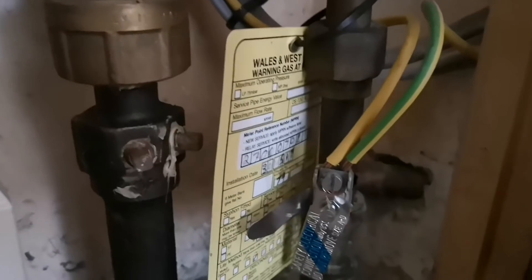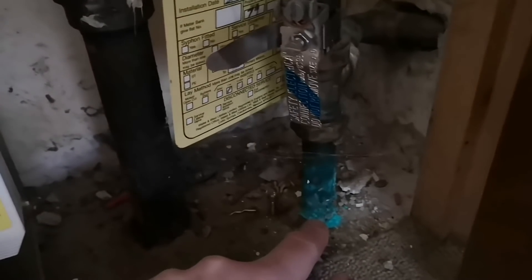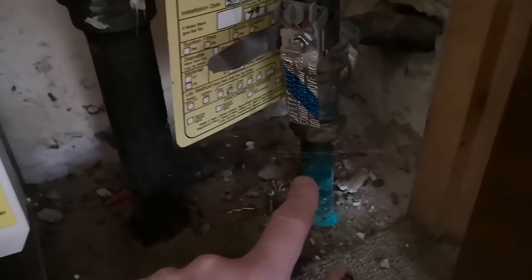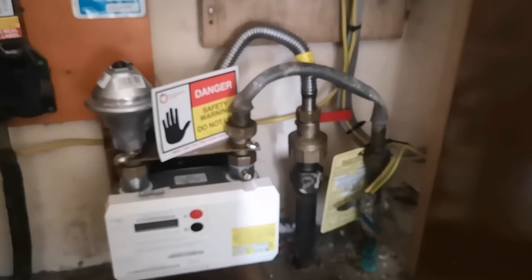You can see it's all old fittings, probably from when the house was originally done. I think these are 1940s houses, so it won't be original but it won't be far off. We've got the lead coming off here with the kink in it, then we've got a tee where someone's put a new combi boiler in and the old supply - there's no other gas appliances in the house, so I have to assume that goes to an old boiler that's no longer in service. The other leg goes under the kitchen units to the boiler that's in an outhouse.